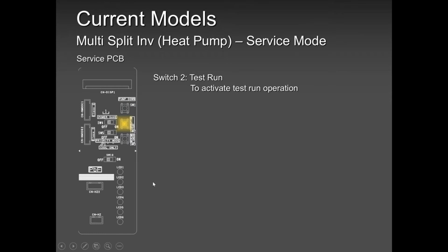This is another button, test run, guys. Test run is a good button that we always use to test the system to see if it's working fine, if there is enough refrigerant, if there is a problem with the compressor, if there is a problem with anything. So what test run basically does is make the compressor run at a very high frequency, probably at the maximum frequency. Okay.